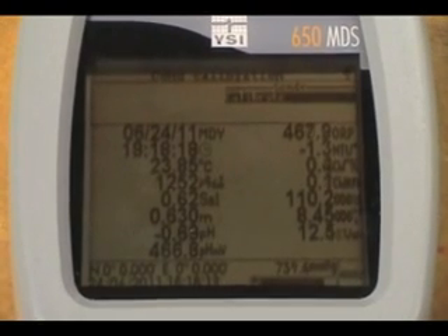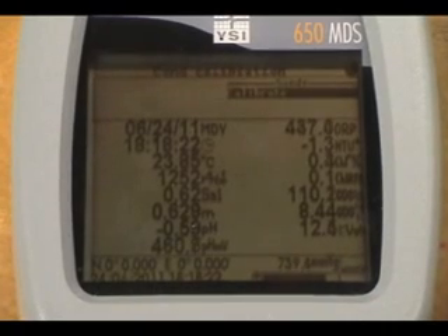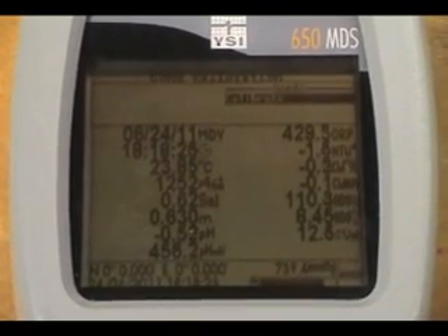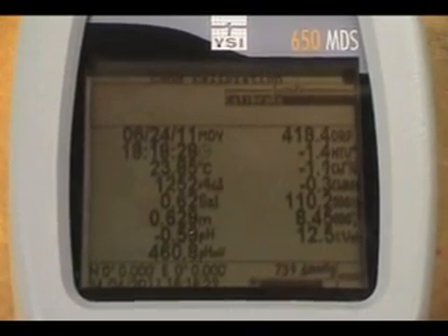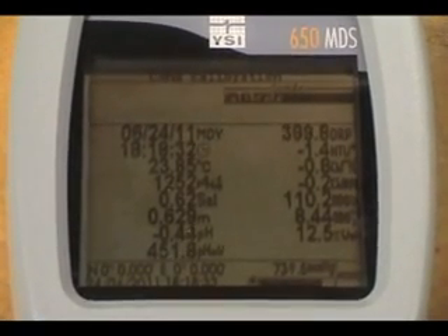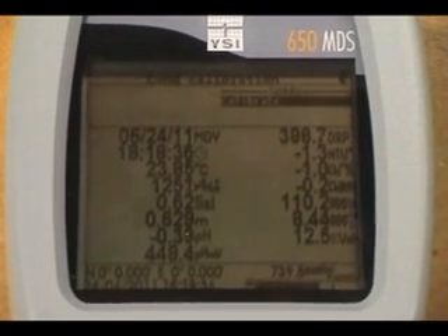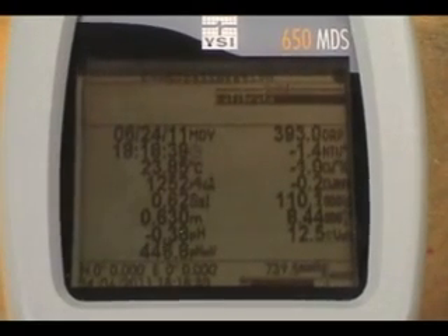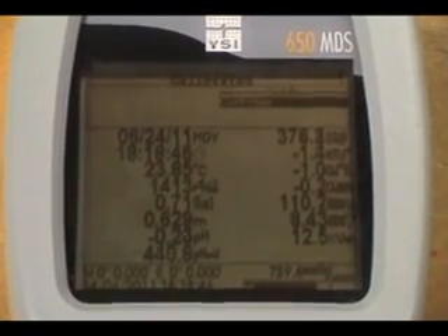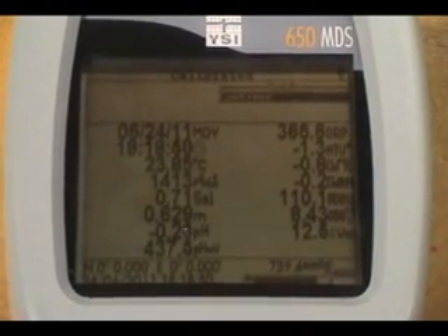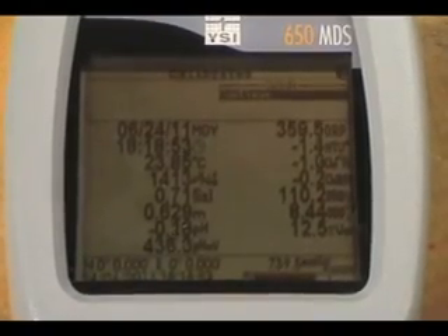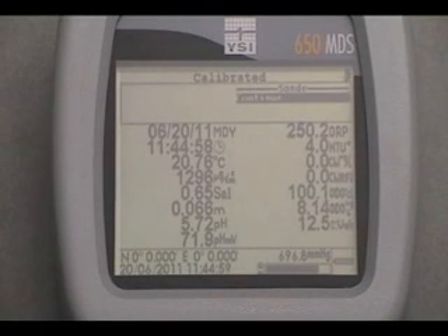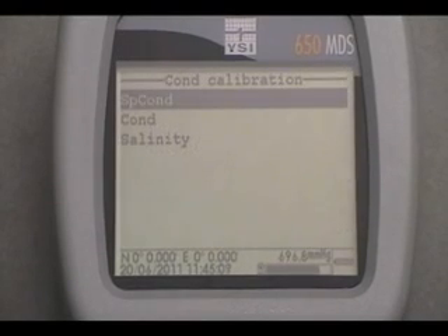When readings are stable, record the pre-calibration value of conductivity in microsiemens per centimeter. Step 10. Highlight Calibrate. Once the temperature reading is stable and the conductivity reading is stable, press Enter. Step 11. Record the post-calibration conductivity value in microsiemens per centimeter on the calibration worksheet. Also record the temperature value in degrees Celsius from the sonde on the calibration worksheet. Step 12. Record the conductivity cell constant on the calibration worksheet. First, press Enter to continue, and Escape to return to the main menu.